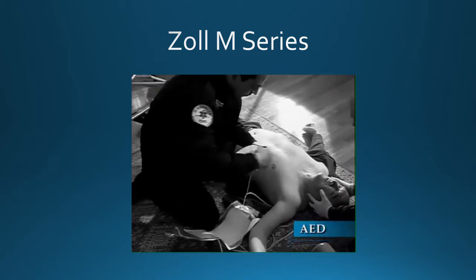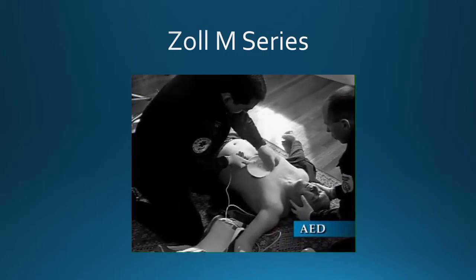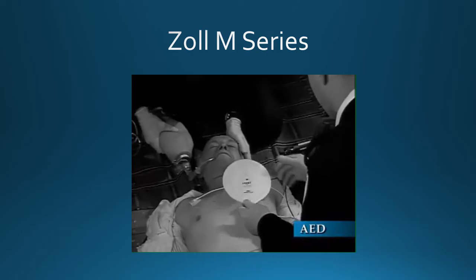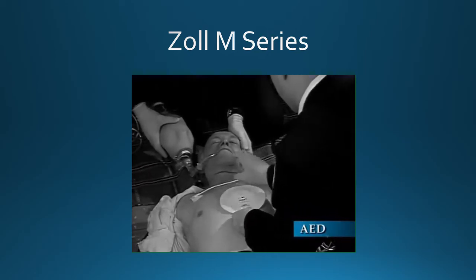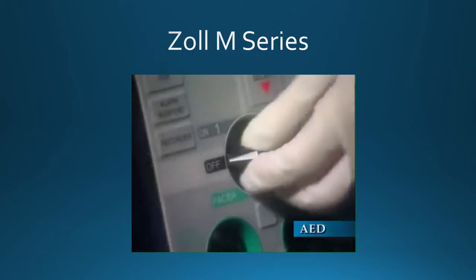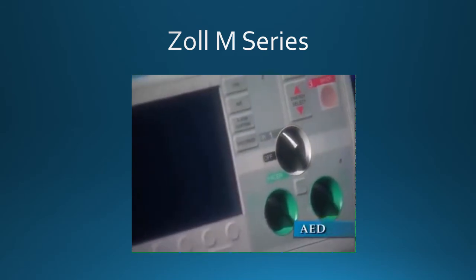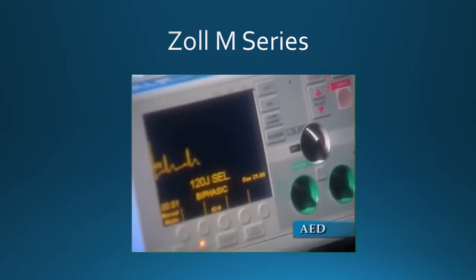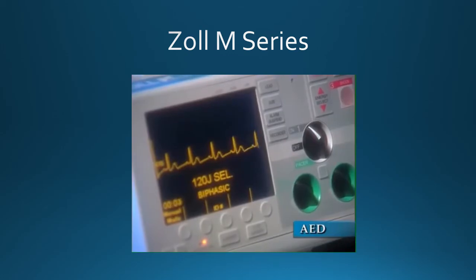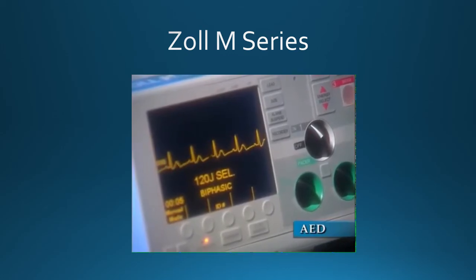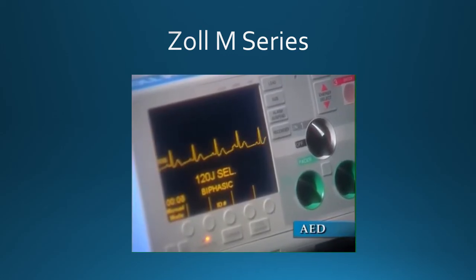Ensure that all MFE pads are making good contact with the patient's skin and are not covering any part of the ECG electrodes. Set the selector switch to on. The unit will beep 4 times to indicate that it has passed the power on self-test. If the audio recorder is present, the unit will begin recording audio data.